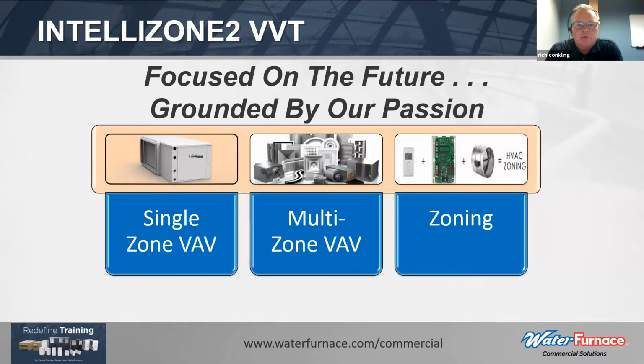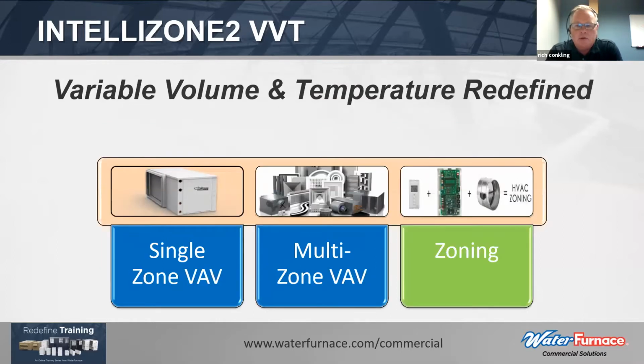The one that's not shown up here on the screen today is one that was just recently released a few weeks ago, and that's a dedicated outdoor air system. So with the factory configurations, we can alter the unit to be applicable to single zone VAV, multi-zone VAV, zoning, and dedicated outdoor air systems. And today we're going to be talking about the zoning system, the IntelliZone 2 zoning system.